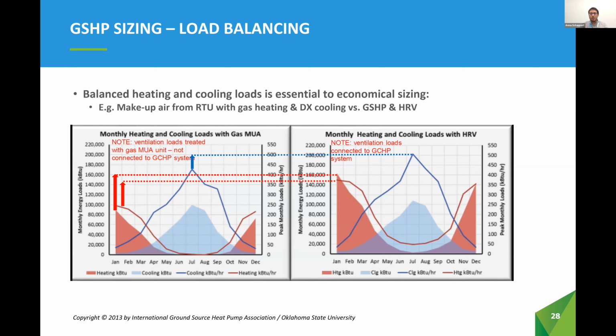Let's consider a commercial building example. In these charts, peak heating and cooling loads are represented by the solid lines, while heating and cooling energy is shown by the shaded area. On the left, cooling energy is approximately 25% larger than the heating, while the peak cooling demand is about 70% larger. The chart on the right is the same building with the additional load of conditioning ventilation air added to the ground source system, along with heat recovery on that ventilation air.